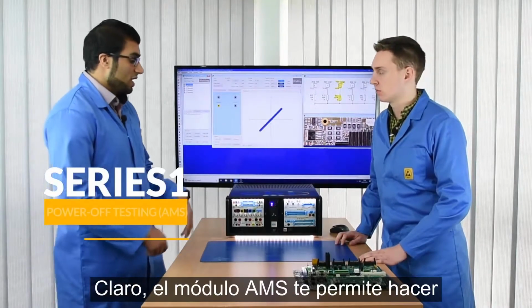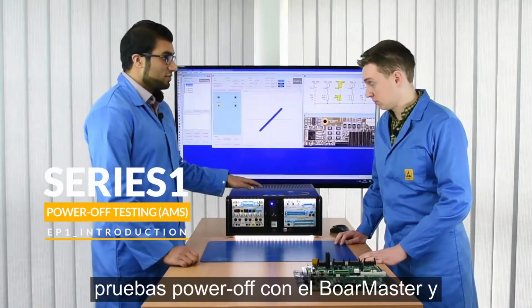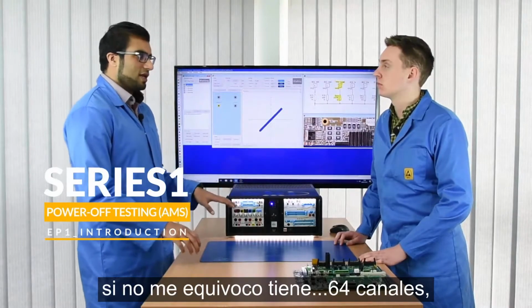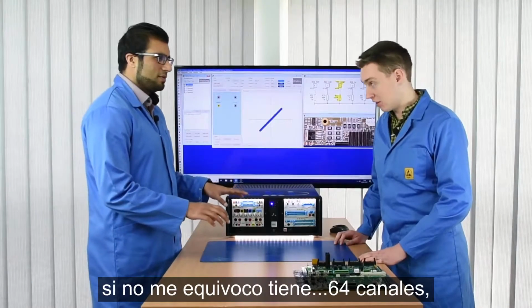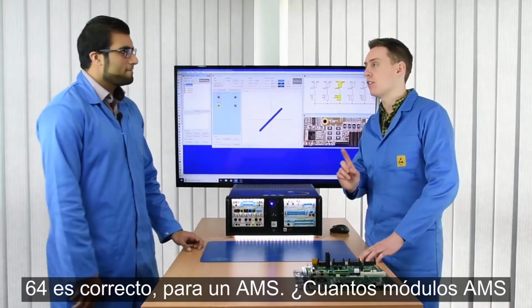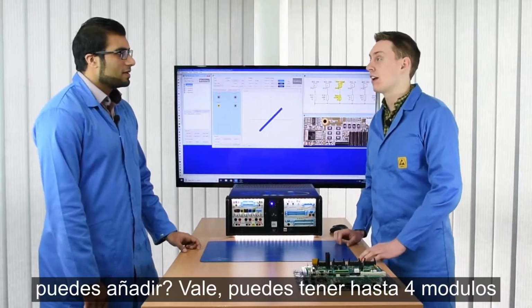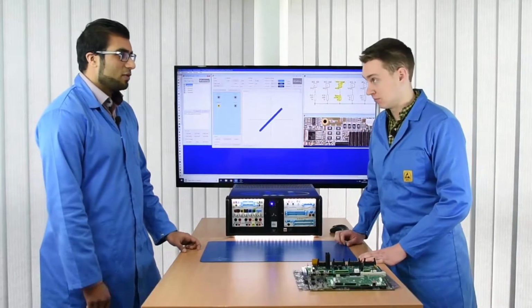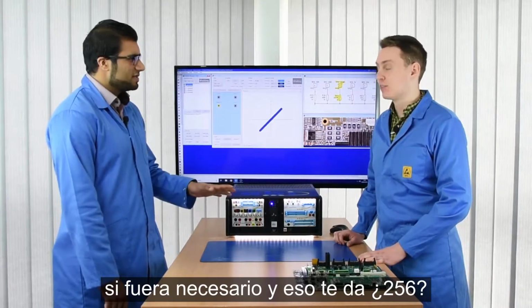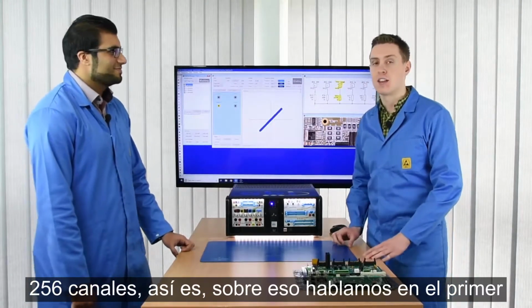Sure. So the AMS allows you to do power off testing through the BoardMaster. And if I'm correct, the AMS has 64 channels? 64 channels, that's correct, for one AMS. How many more AMSs can you have? Right, so you can have up to 4 if required, and that would be 256. 256 channels. Okay, so that was the first episode.